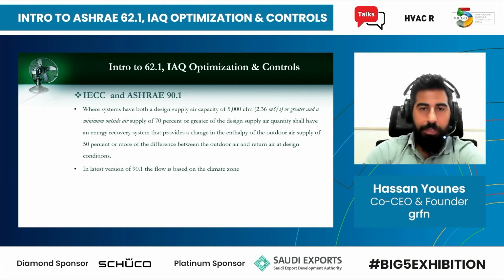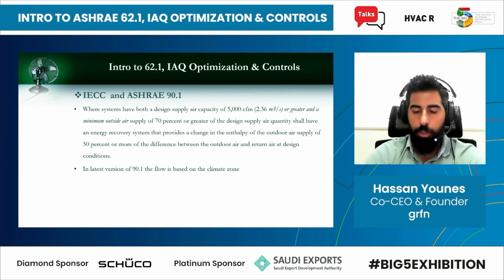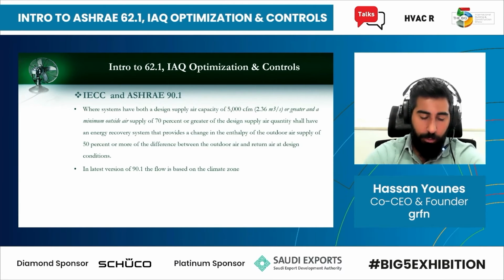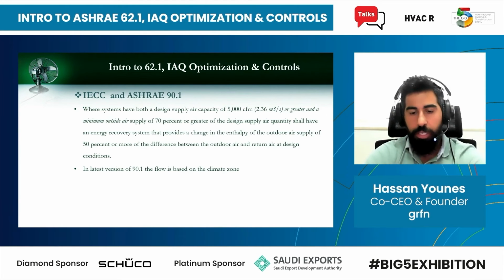If we look at the requirements, normally when it comes to energy efficiency for buildings, the go-to standard is ASHRAE 90.1. In terms of code, it's the International Energy Conservation Code. It normally would require heat recovery for certain capacities. In the newest version of 90.1, it depends on the climate zone. So if you take Dubai as an example, it sits in climate zone 0B, which is extremely hot and dry. They call it dry because there's not a lot of rain. This is how they classify dry and wet zones. It depends on the amount of rainfall, not on the humidity levels.